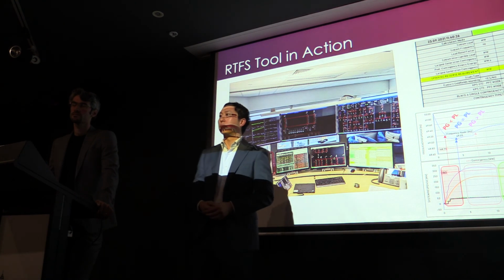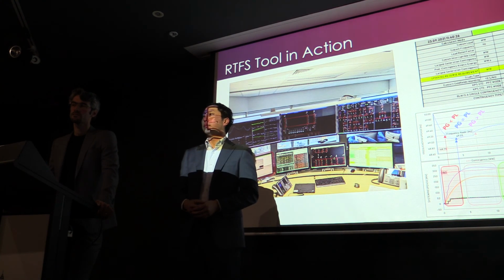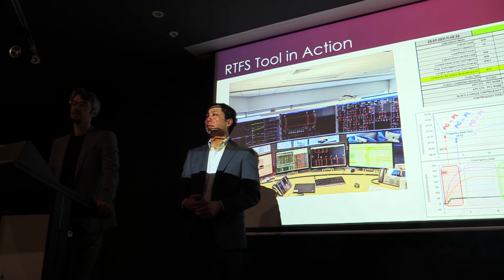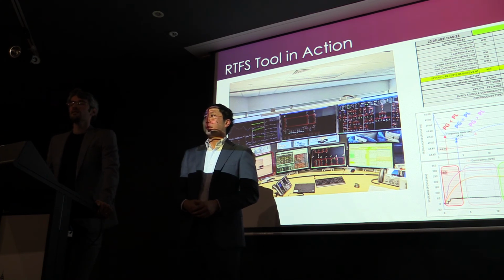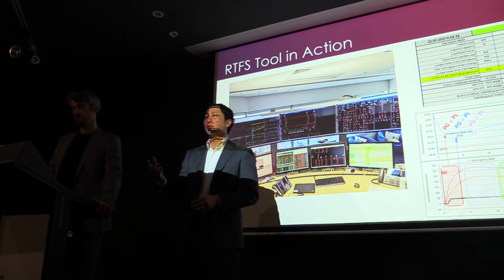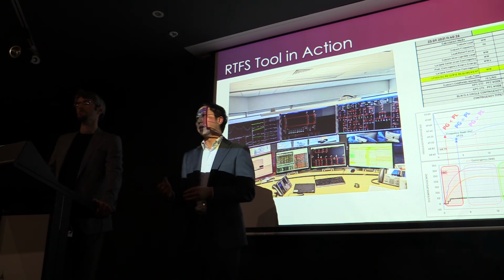So is the emerging problem now less about spinning reserve and more about actually droop response itself? You know, like you've got to have that fast response in reaction to an event. You know that if you survive the first 5 seconds, probably the spinning reserve's kicking in and saving you anyway. It's all about that first few seconds, you're trying to go, all right, we need to have that first 5 seconds covered. Pretty much just five. So droop response and spinning reserve are the same thing. Yeah, in this sense, but, yeah.